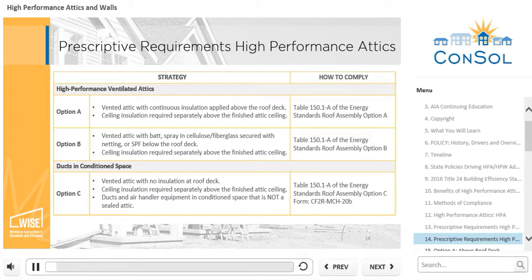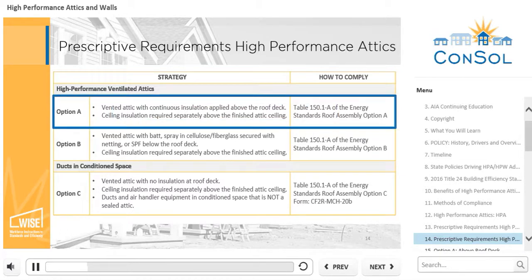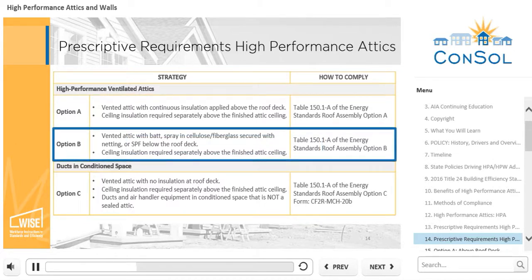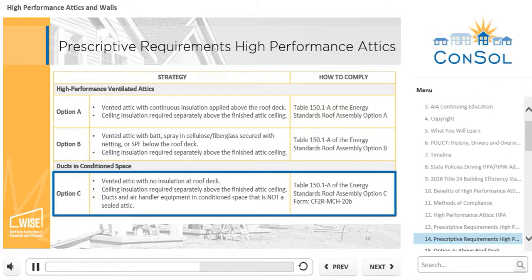To comply prescriptively as a high-performance attic, there are 3 options. Option A for vented attics with continuous insulation above the roof deck and ceiling insulation separately above the finished attic ceiling. Option B for vented attics with batt, spray-in insulation with netting, or SPF below the roof deck with ceiling insulation separately above the finished attic ceiling. And Option C for vented attics with no insulation at the roof deck, ceiling insulation separately above the finished attic ceiling, and ducts or air handler equipment in conditioned space that is not the attic. Let's look at each of these options in detail.